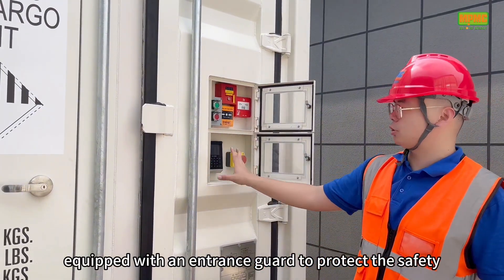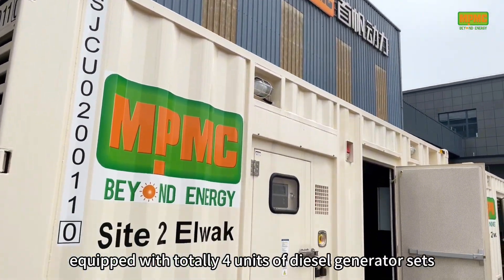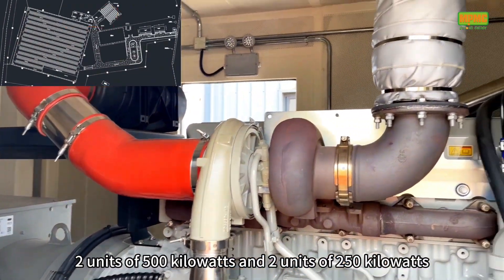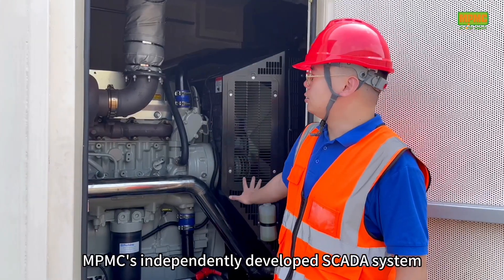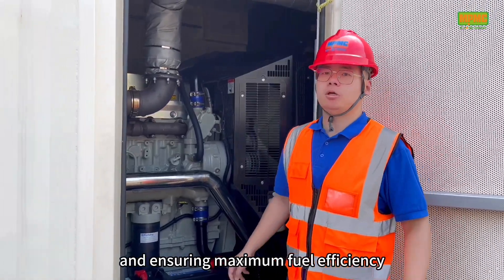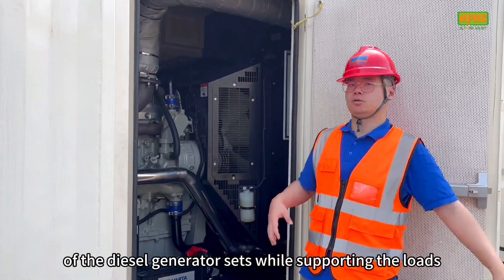This battery container has only one entry and exit point, equipped with an access control system for safety. The power plant is equipped with a total of 4 diesel generator units — 2 units of 500kW and 2 units of 250kW — as backup power to coordinate with PV panels and BESS. The system connects with MPMC's independently developed SCADA system, realizing real-time energy management and ensuring maximum fuel efficiency of the diesel generators while supporting the loads.